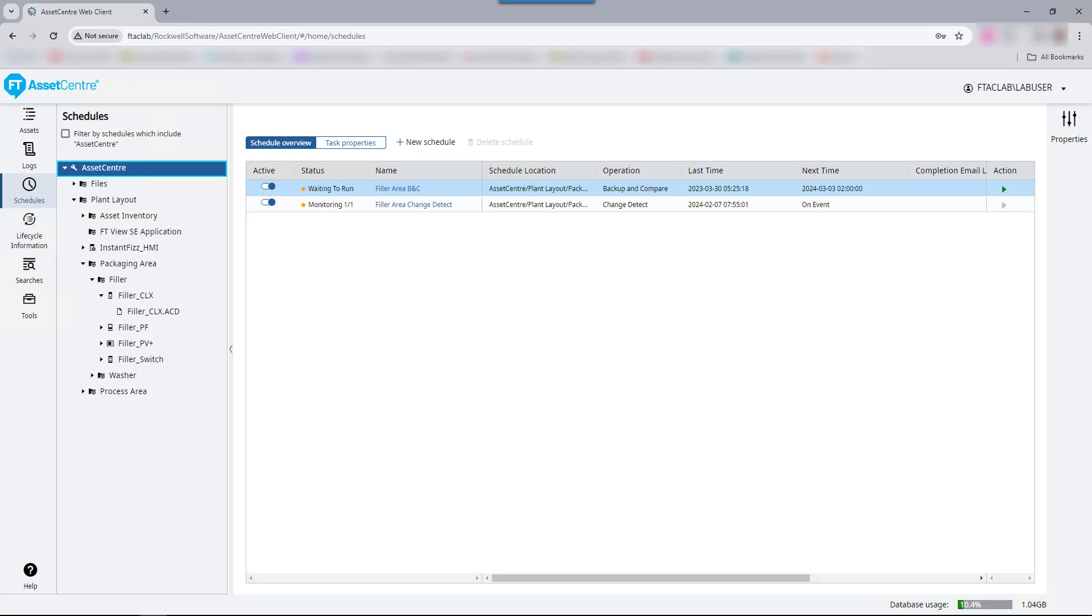Factory Talk Asset Center will automatically initiate the upload from an asset, compare the current configuration file to the last known good version in an archive, and create a differences report if any exists. This report is stored in the Factory Talk Asset Center logs and can optionally be emailed as well depending on the user's preference. A configuration with differences can be immediately added to the archive automatically incrementing the version.